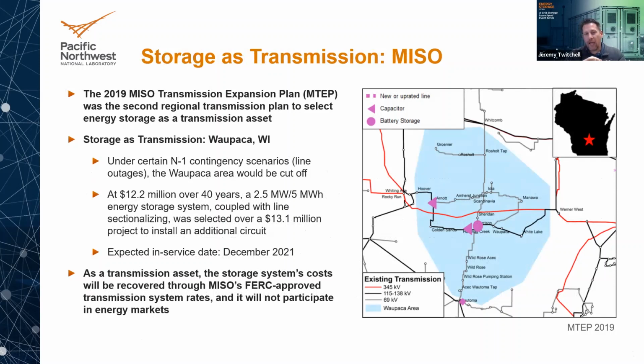That's a 345 kilovolt line. In their plan, they found that if there was an outage somewhere along that 345 kV line, the entire Waupaca area could be cut off. So they looked at a couple options. They looked at adding additional lines in the system, but found that the most cost-effective option would be to put a storage system in the middle of Waupaca, that purple dot you see, and then sectionalize the line. Effectively add some capacitors so that if there is an outage, instead of Waupaca being dropped, the lines can switch. One line can switch to be fed by the line still active on the other side, and the other side of town can be supported by the energy storage asset. This project cost an estimated $12.2 million compared to $13.1 million for building additional lines.